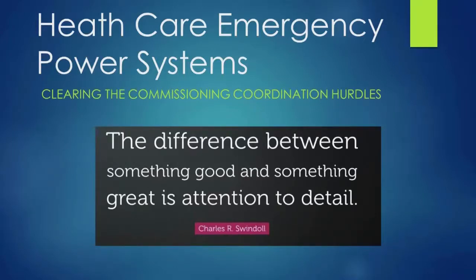Very rarely do I see it, though I'm starting to see it more—electrical sequences of operation for things like fire alarm devices, but specifically for emergency power supply systems, it's hit or miss. I am seeing it in contract documents more than originally, but usually I still have to ask for more detail or request a sequence of operation because it's just not there. It's a conversation we have to initiate; more often than not we don't see it automatically, so I like to talk with the engineer of record and the owner about how we can get this information.